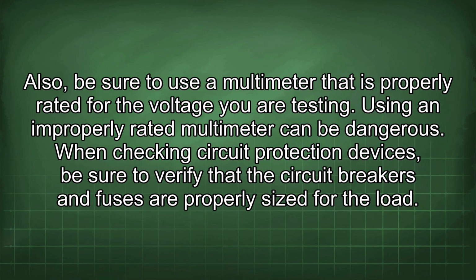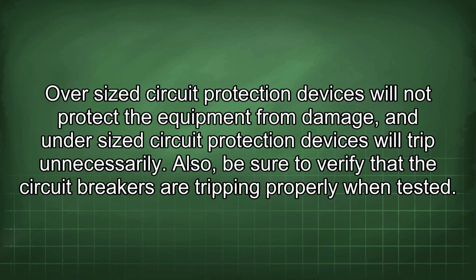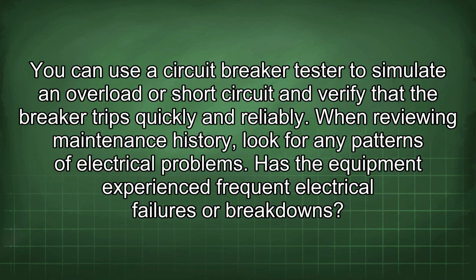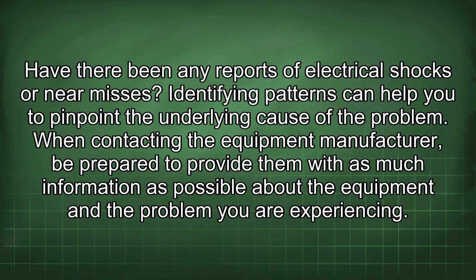When checking circuit protection devices, be sure to verify that the circuit breakers and fuses are properly sized for the load. Oversized circuit protection devices will not protect the equipment from damage, and undersized circuit protection devices will trip unnecessarily. Also, be sure to verify that the circuit breakers are tripping properly when tested. You can use a circuit breaker tester to simulate an overload or short circuit and verify that the breaker trips quickly and reliably. When reviewing maintenance history, look for any patterns of electrical problems. Has the equipment experienced frequent electrical failures or breakdowns? Have there been any reports of electrical shocks or near misses? Identifying patterns can help you to pinpoint the underlying cause of the problem.